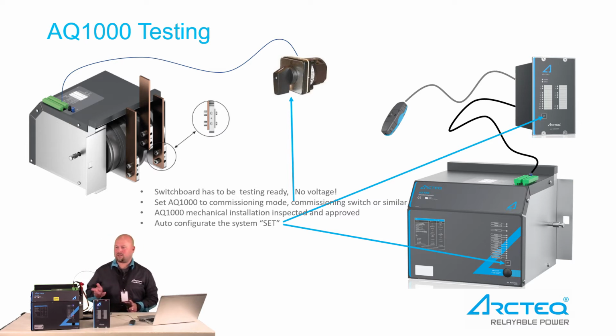Okay, a few reminders. Many times said probably already, but the switchboard has to be testing ready. No voltage. Set AQ1000 to commissioning mode, commissioning switch or similar. AQ1000 has to be mechanically installed properly. It has to be inspected and approved. Verification has to be done that this is properly installed, bus bars are connected properly, there are correct insulation levels and so on. And after the fiber optics is connected to the relay, press the set button for 3 seconds from here, and from the relay itself it will start auto-configurating, and after auto-configurating everything is ready and done.